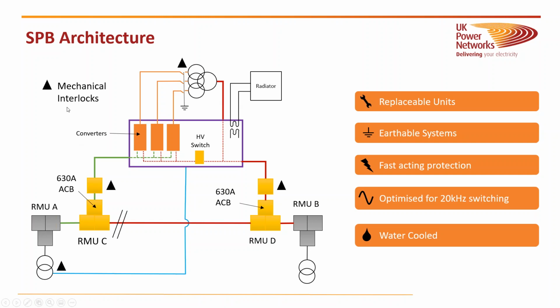The last bit to talk about here is the interlocks. Again, to prove the system is dead when you're working at 11 kV, you need to prove everything's dead. So we've got these mechanical interlocks, and there are a couple of different energy supplies. Obviously you've got each feeder, but you've also got this LV supply, which is used to charge the DC bus bar when it starts up. So it's very important that we've got these interlocks in place to make sure that no one can access the building that this SPB is in when it's in operation, and that actually includes commissioning as well.